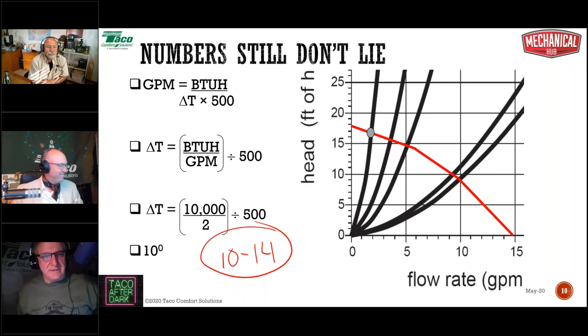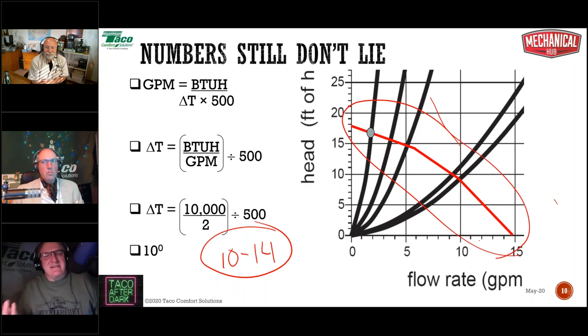Is this what we want? Is this what's best for the system? Is this just something that happens and we can't do anything about it? No, this is just a fact of life caused by us overpumping the zones. We have a chronic overpumping problem in our industry. I'm not going to say misunderstanding, but it's a, hey, the three-speed pump's the only pump I'll ever need. I put it on high because I ain't never had no problems, so we'll be fine, all right? And you're not going to have any problems if you define problems as people freezing to death and blaming you. In that case, you can say, I put it on 3-speed, it works, my job here is done.